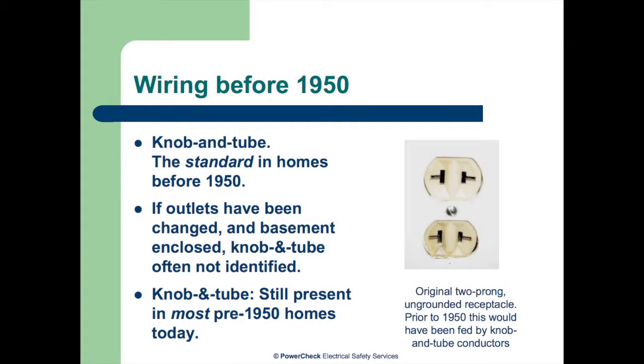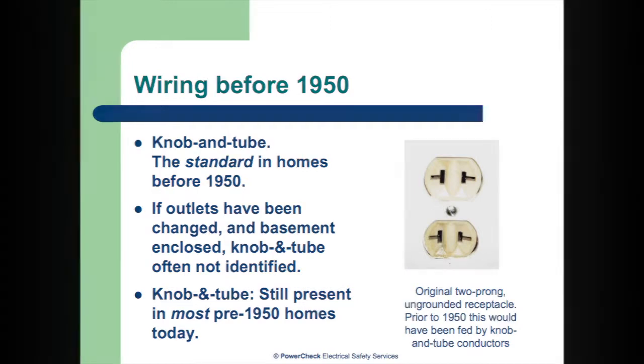Knob and tube. Wiring before 1950. This was the standard in all houses. If we see a house like this and it's got the old two-prong receptacles, we test the wire behind the walls. In 99% of it, the old wiring is tickety-boo, and the outlet itself is fine for what it is, which basically means you can plug in something with two prongs, which is a light. And that's what it was designed for.